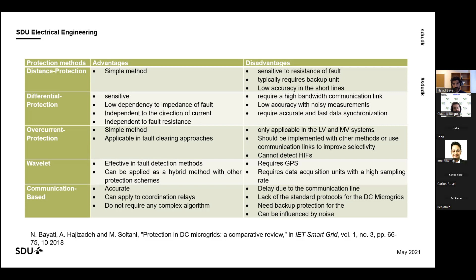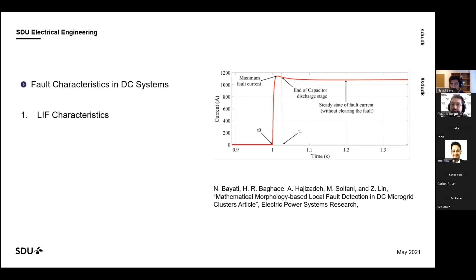So how is the fault behavior that we talk about, the high rate of rise and the high change of the current in the DC microgrids? You can see here a DC fault in a DC microgrid. As you can see, the fault current reaches the maximum value very fast. You can see the slope is more or less infinite. So it's going very fast. But in the AC systems, we have 10 cycles or 200 milliseconds for this one. So it's really hard and harsh to clear the faults on these systems.